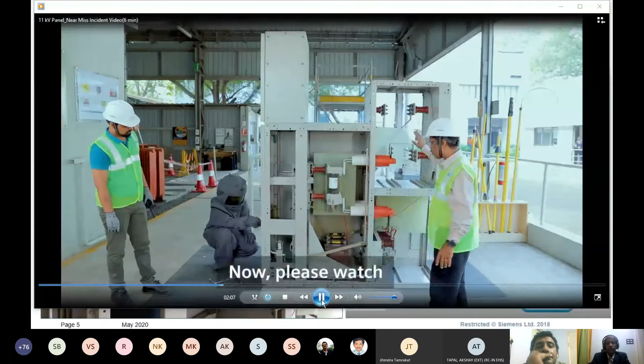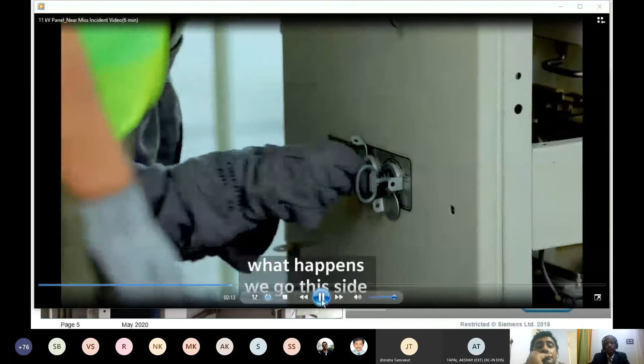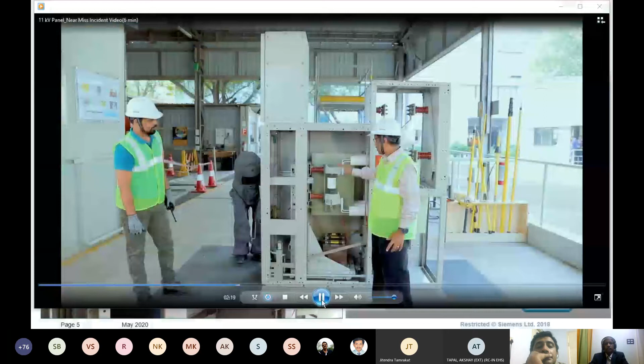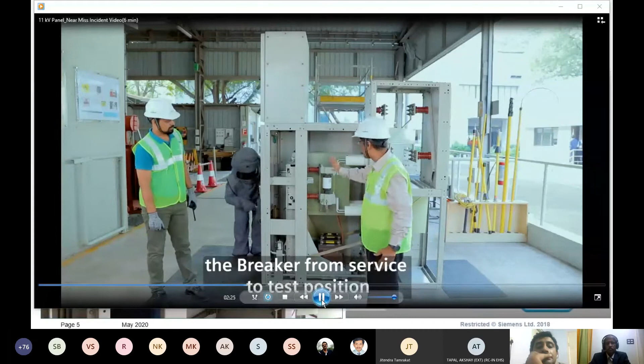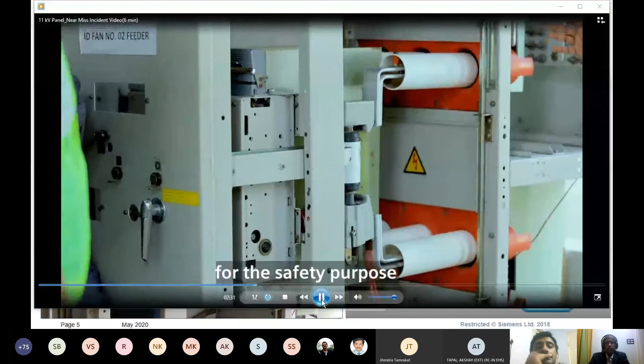Using the double-bit key, he is opening the lock. Now please watch what happens when the breaker moves from service position to test position, because this side bus bar is totally charged up to here. Now he is removing the breaker from service to test position. You can see there will be a movement of the shutter for safety purposes.